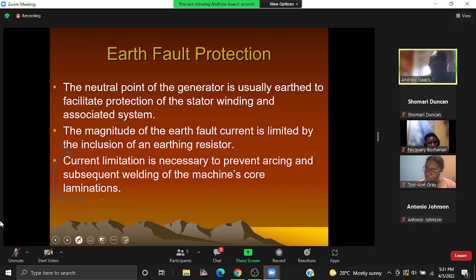But while I am limiting the current, going back to what you went through for lab two, when we were looking at overcurrent relays, we saw that the higher the current, the faster the operation for your inverse relays. So if I'm going to reduce the fault current, it means that I'm going to reduce the level of responsiveness of the protection system to the fault. So we have to find a way of countering that natural phenomenon.